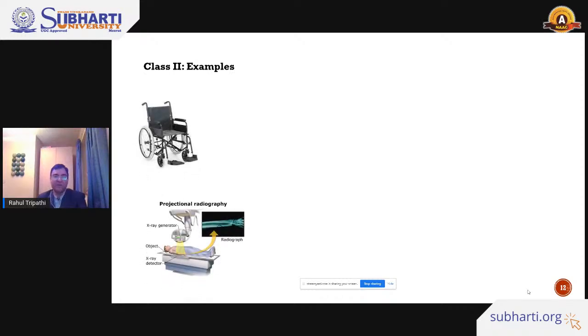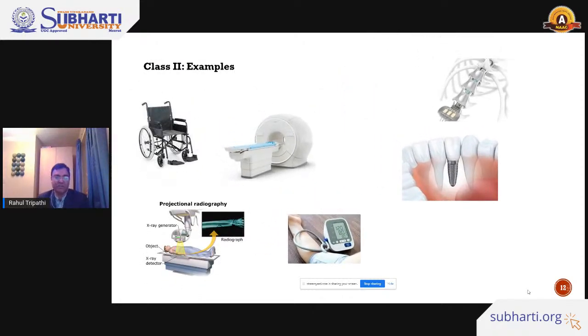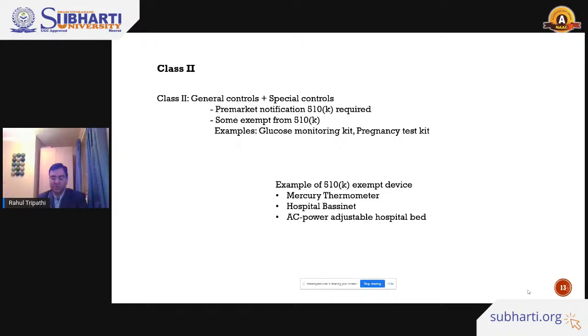Now, the class 2 examples. So class 2 examples, as I discussed, like wheelchairs, radiography, MRI machines, BP instruments, spinal implants, dental implants. Those fall under the class 2 medical devices, and those class 2 medical devices have a regulatory pathway with general controls or special controls. So the general controls I already explained: sometimes you are exempted from the 510k form, and sometimes you need it based on the regulatory requirements for class 1.